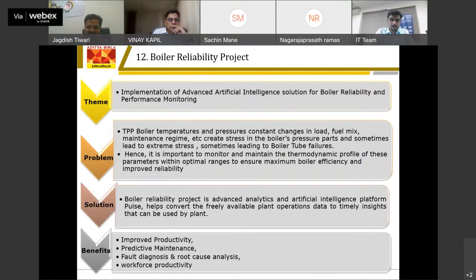Coming to the digitalization front, sir, we have introduced the boiler reliability project, and we have collaborated with Exact Space, which is a startup. By this, we are measuring our key parameters, and they are giving us predictions on which parameter is deviating, like superheater spray flow, if there is a problem, whether it is increasing or decreasing. Then they monitor APH exit flue gas temperature, PF and fans mechanical health, and boiler feed pump mechanical health, and they are also monitoring the boiler before shutdown. They are monitoring how our boiler is operating. By this, they are giving us reports, and on the basis of the reports we are working, and in shutdown we are doing modifications so that our reliability is maintained.